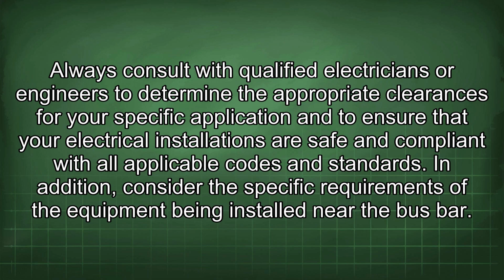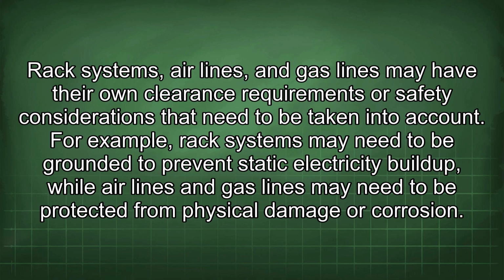In addition, consider the specific requirements of the equipment being installed near the bus bar. Rack systems, air lines, and gas lines may have their own clearance requirements or safety considerations that need to be taken into account. For example, rack systems may need to be grounded to prevent static electricity buildup, while air lines and gas lines may need to be protected from physical damage or corrosion.